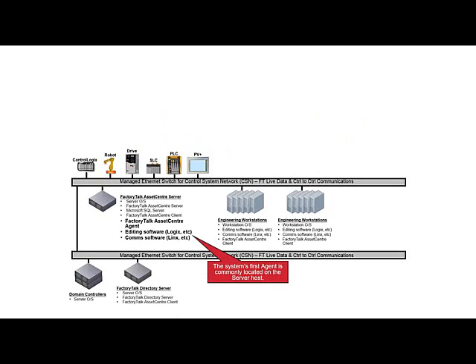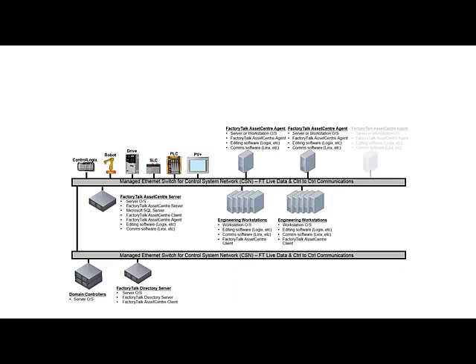It is common to co-locate the first FactoryTalk Asset Center agent with the FactoryTalk Asset Center server. When doing so, the server host will have the agent itself installed on it, as well as any of the supporting software. As more agents are added, more hosts will become necessary, as a single host can only support a single agent. Also note that Rockwell does not recommend co-locating the agent with an engineering workstation — while the supporting software needs are oftentimes the same, the agent's resource requirements can interfere with an engineering workstation's normal operation. For the purposes of determining agent count, estimate that a single agent can service around 100 assets every 12 hours.